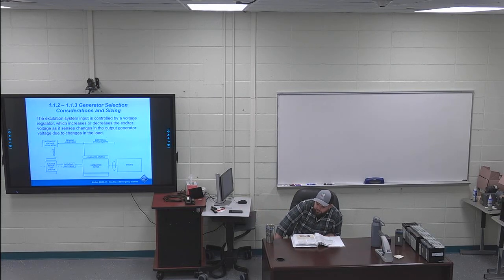On the right hand side of page 5, the last paragraph before 113, the last sentence is highlighted. Applications with the following types of loads and similar devices may also require that the generator be oversized. If you have fire pumps, I've got fire pumps highlighted. The building that I worked at Goodyear was 52 acres under roof. Massive building. They had to have fire pump stations at all 4 sides of the building. I would have to walk around to each one of them, start them up, and make sure they had their own backup generators in those pump houses.